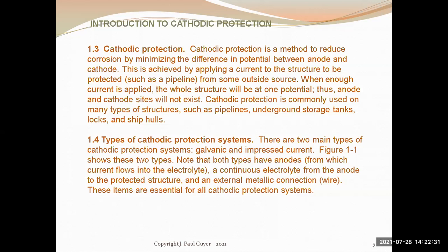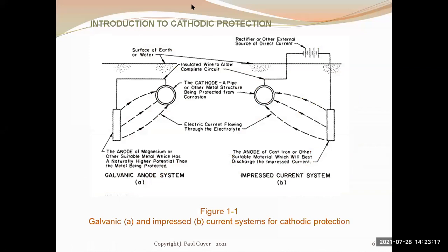That's the basis of your corrosion protection: that your pipe or tank, 15 years in the future, is going to be adequately protected. Some percent of its surface area is going to be adequately protected by the coating that you apply, and the remainder of the surface area of your cathode structure needs to be protected using a cathodic protection system. Now, there are two types of cathodic protection.